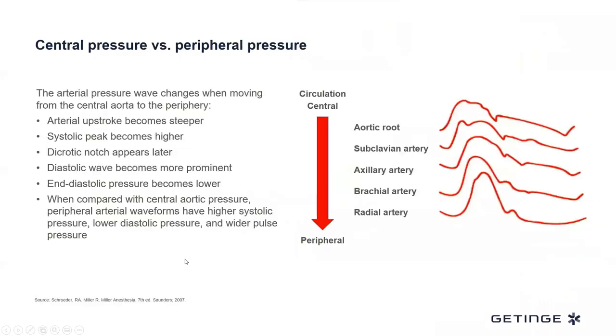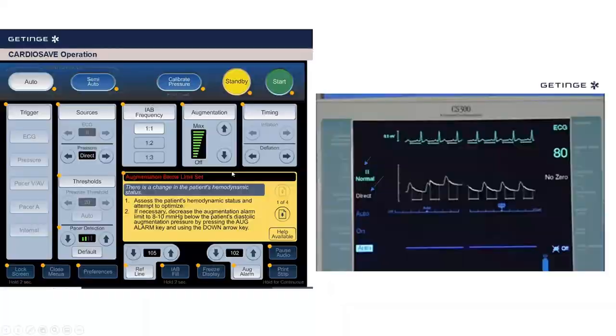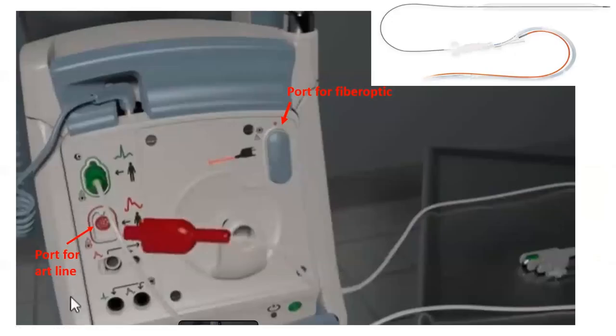That's not ideal because radial pressure is different than aortic pressure. So you're not getting real-time adjustments of the aortic augmentation and the assistance, because with the peripheral pressure you get higher systolic pressure, systolic amplification, and a lower, more delayed dicrotic notch and diastolic pressure. So you can use a radial line, but the waveform will become suboptimal and the augmentation adjustment based on that waveform may become suboptimal. But that could be the only thing you can do short of replacing your whole balloon pump if your arterial lumen is clotted and you don't have a fiber optic line.